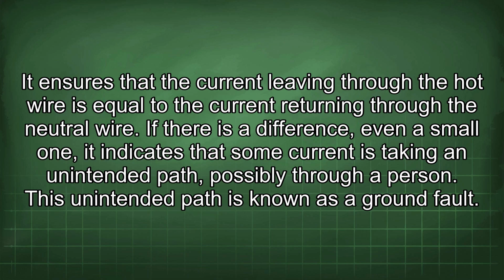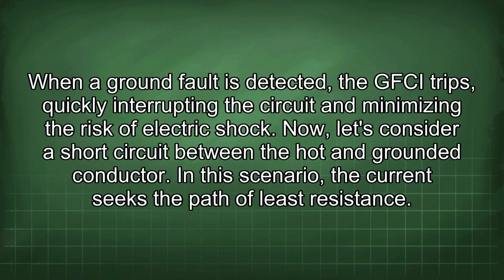If there is a difference, even a small one, it indicates that some current is taking an unintended path, possibly through a person. This unintended path is known as a ground fault. When a ground fault is detected, the GFCI trips, quickly interrupting the circuit and minimizing the risk of electric shock.